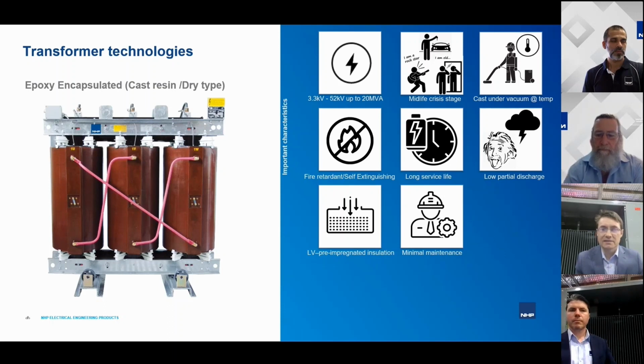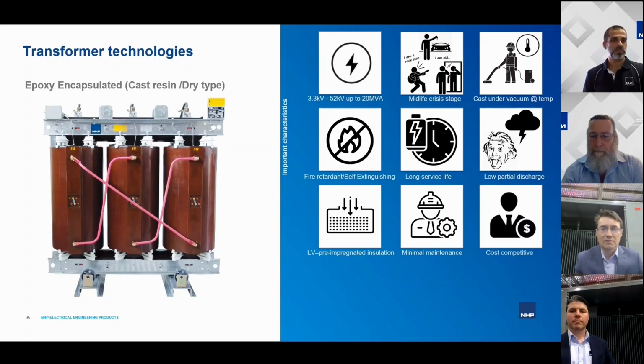But the other factor that will change a lot is dust. So as such, cast resin transformers are not ideal for dusty environments, and this is where it can result in quite frequent maintenance and removing the dust. But in general, in clean installation environments, especially indoors, that's really a very minimal requirement for dust cleaning. Other than that, there are no maintenance activities. The only other one is just a visual inspection of the transformer, to make sure there's nothing suspicious, and the testing of the over temperature protection relay. So as you can see, requirements are pretty minimal, especially if the environment is clean.